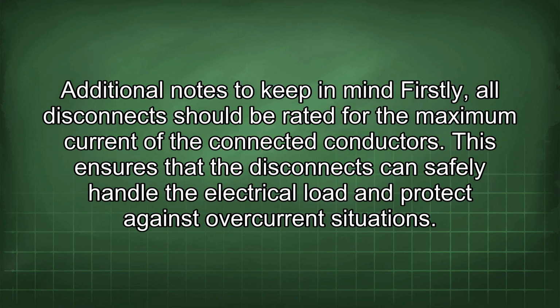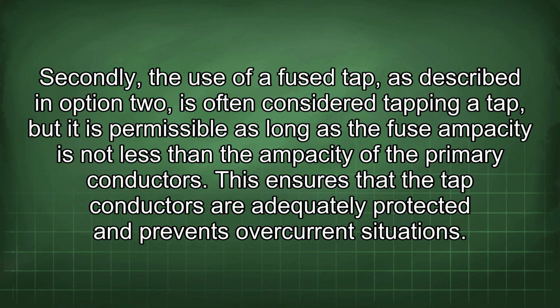Additional notes to keep in mind: firstly, all disconnects should be rated for the maximum current of the connected conductors. This ensures that the disconnects can safely handle the electrical load and protect against overcurrent situations. Secondly, the use of a fuse tap, as described in option 2, is often considered tapping a tap, but it is permissible as long as the fuse ampacity is not less than the ampacity of the primary conductors. This ensures that the tap conductors are adequately protected and prevents overcurrent situations.